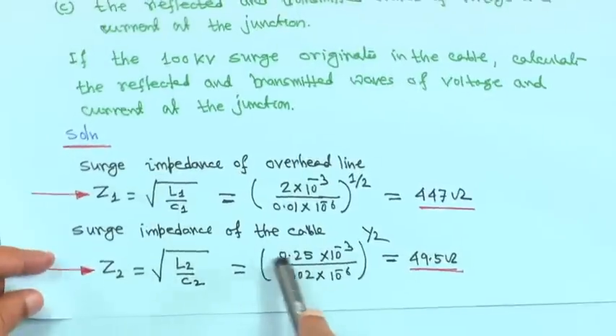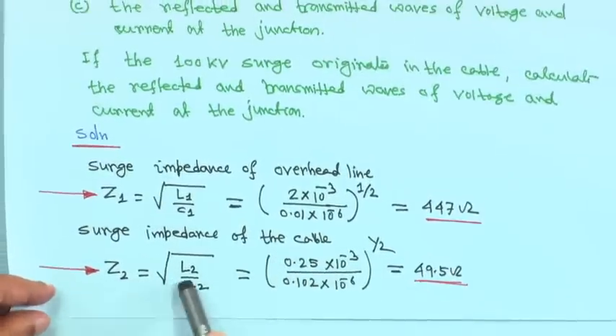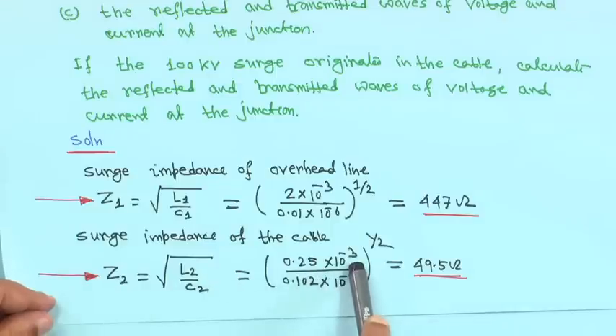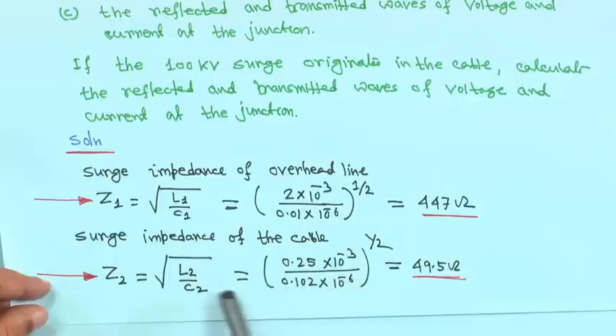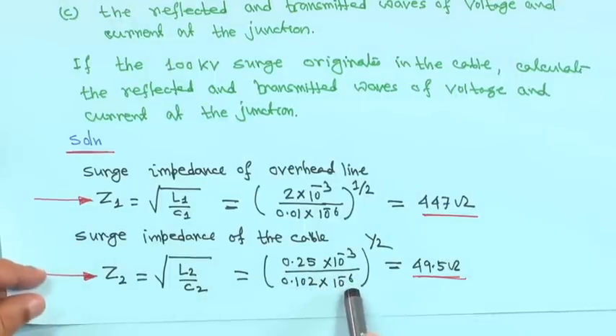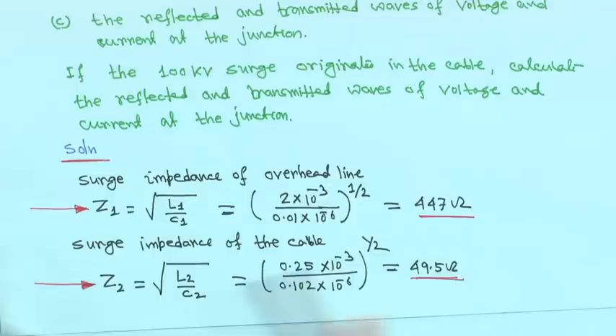Similarly, surge impedance of the cable Z2 equals root over L2 upon C2. L2 is 0.25×10⁻³ henry and C2 is 0.102×10⁻⁶ farad. Taking the square root gives Z2 equal to 49.5 ohms.